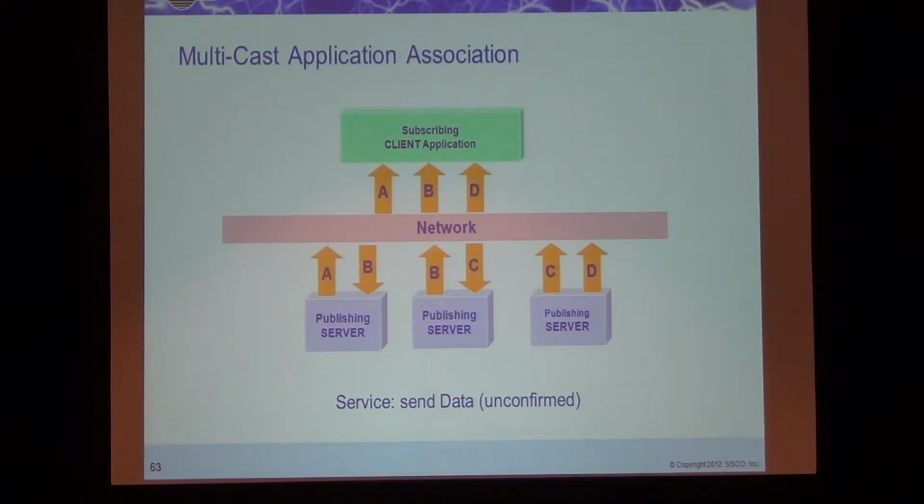There's also a multicast type of communication environment where the devices can simply publish the information that they have about their status and communicate that status very, very fast to many different devices and applications quickly. So the idea here is that if you have a server that's publishing information about itself and what state it's in, other devices that need to know that state can receive that information quickly and make control decisions at the level below what a client is involved in.